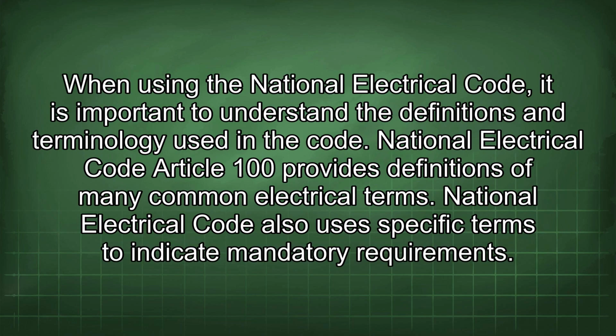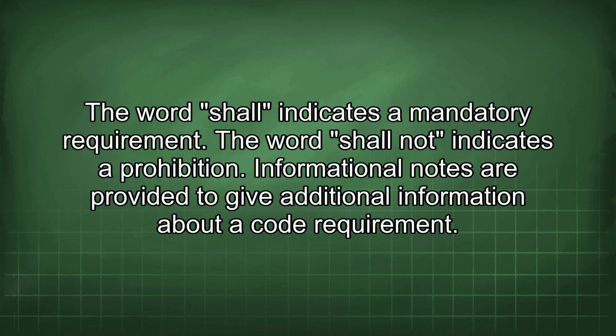When using the National Electrical Code, it is important to understand the definitions and terminology used in the code. National Electrical Code Article 100 provides definitions of many common electrical terms. The National Electrical Code also uses specific terms to indicate mandatory requirements. The word shall indicates a mandatory requirement. The words shall not indicate a prohibition.